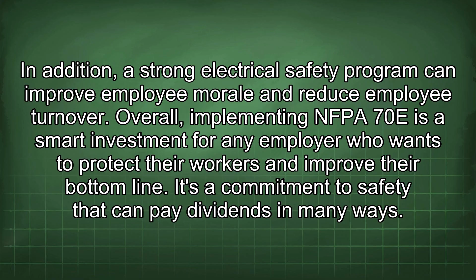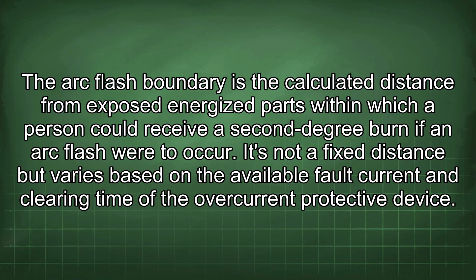Concepts like arc flash boundaries, incident energy, and hazard risk categories are foundational to assessing and mitigating risks. The arc flash boundary is the calculated distance from exposed energized parts within which a person could receive a second-degree burn if an arc flash were to occur.